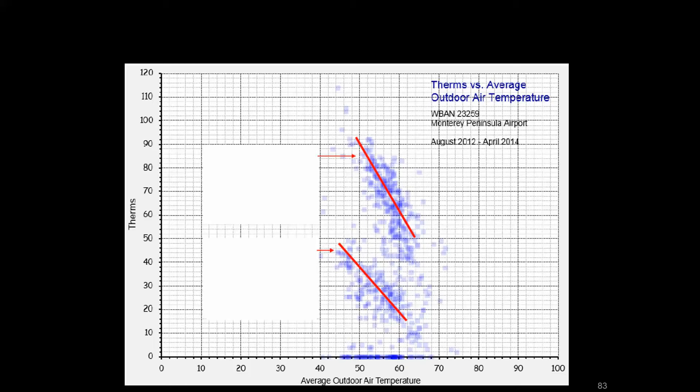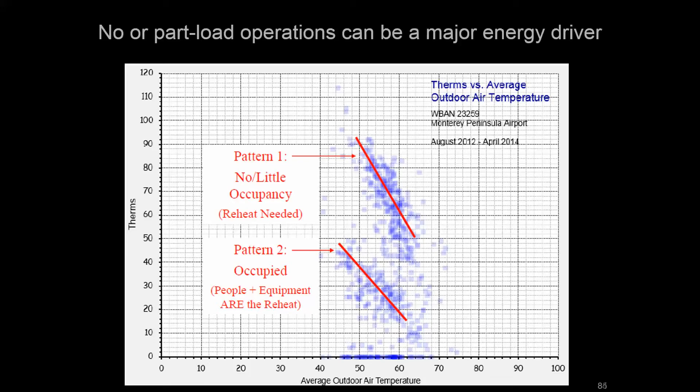One of the tricks that we have to try to determine these things up front is we can do things like plot energy data on something like outside air temperature instead of a time series chart. This is actually one of those charts of a conference space where we're looking at daily therms, daily gas usage, versus daily outside air temperature. You might expect a single plot line - as it gets colder, you use more gas, more space heat is happening. But in this case, you might see that you have two trend lines. It turns out what was happening here was that there was two patterns. There was one pattern where we were at the occupied state, and the people and the equipment were providing that zone load, and there was less reheat needed. And then that top trend was where there was really no or little occupancy, and that reheat was basically providing the zone load to keep the thermostat happy.